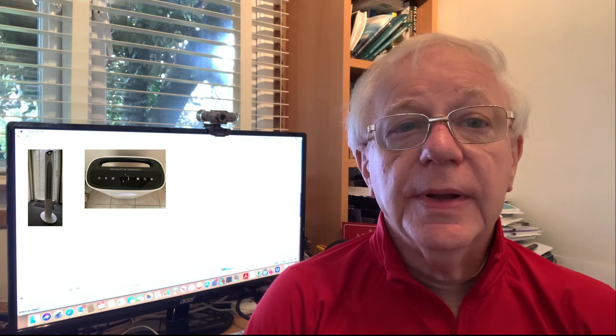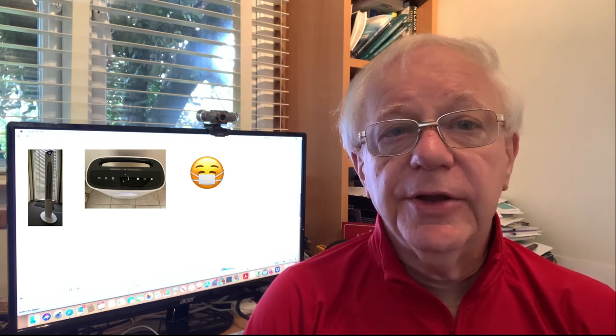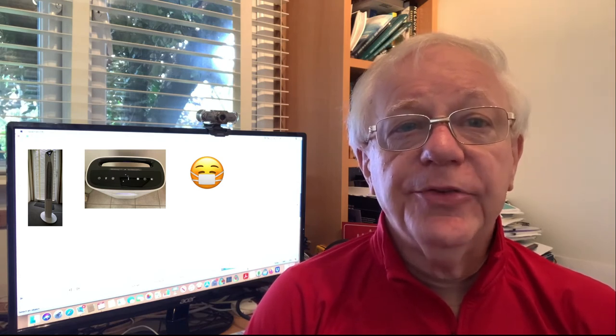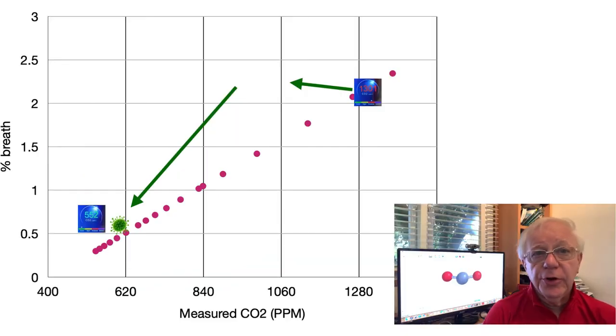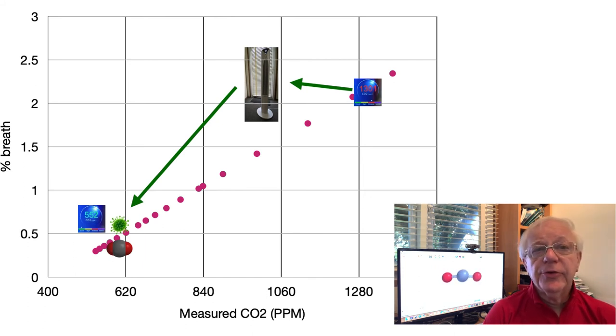So let's consider the effect of having these three mitigation options. This is just one of many combinations you could use. But imagine the room that you are meeting in is flagged by the CO2 meter as having a moderate hazard with a reading of 1301 ppm in this case and is shown in red. An option then is to improve the ventilation represented in this graph by a fan. Potentially that could reduce the CO2 level down to a very good or green band and also reduce the disease carriers to a very similar extent.